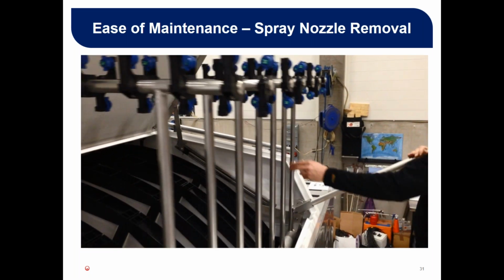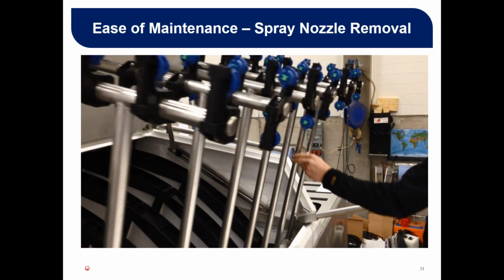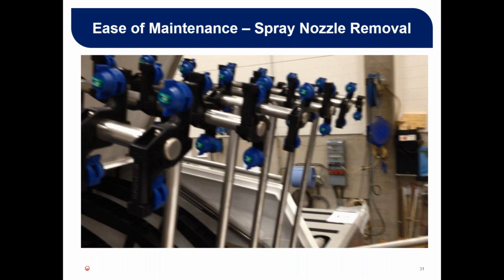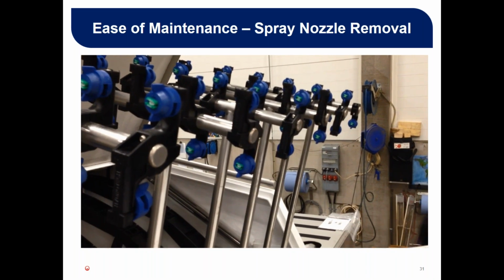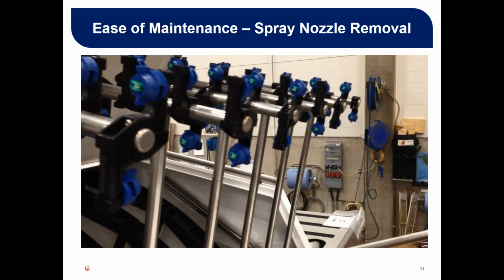Another maintenance thing that we do recommend is visually inspecting the backwash nozzles about once every 2 weeks. So you can see, there's a lever, you can just pull out all of the backwash nozzles. There's a setting on the control panel where you can have a low flow through the backwash nozzles, and you can visually inspect if there's water flowing out.